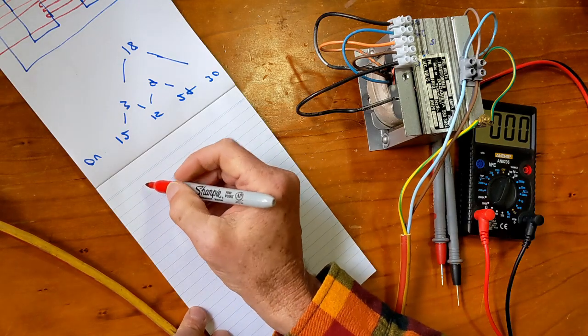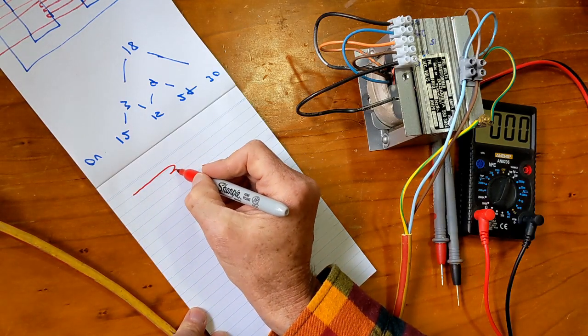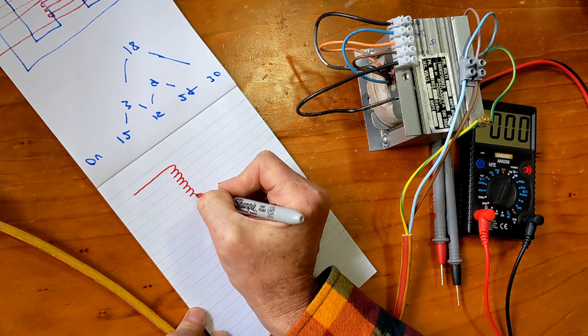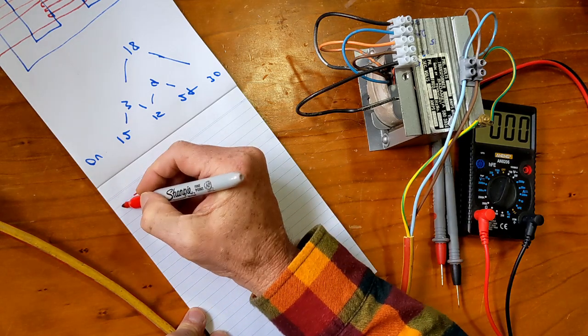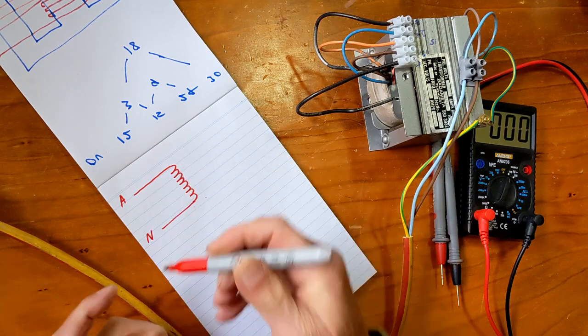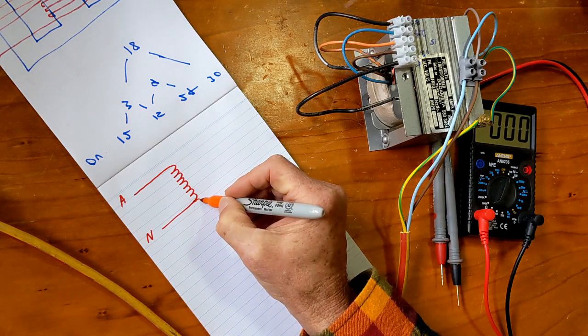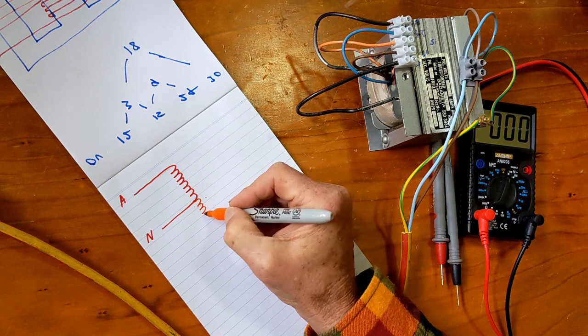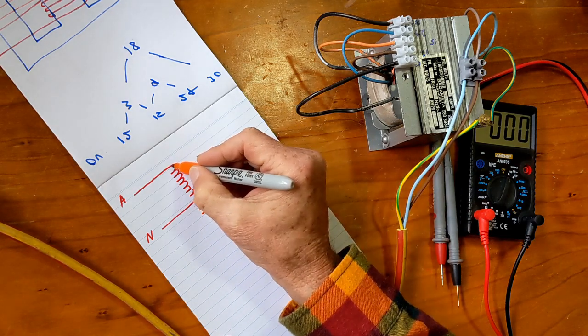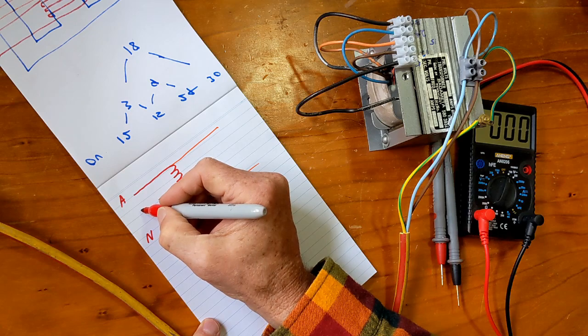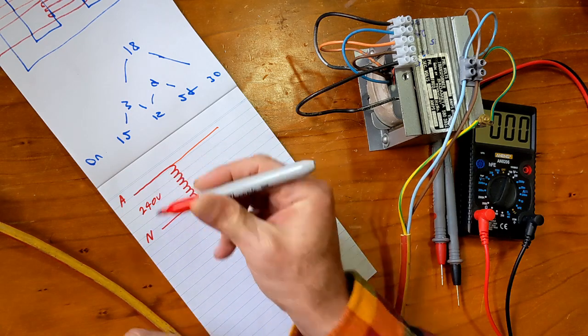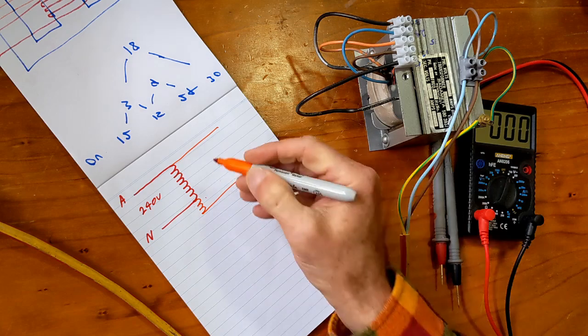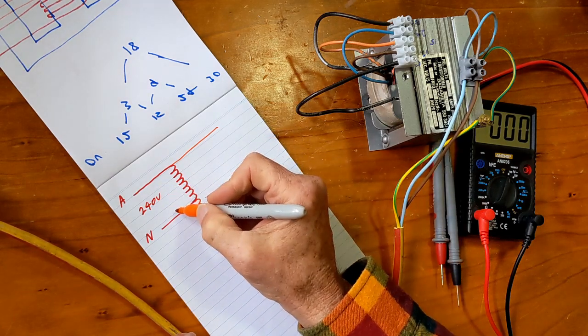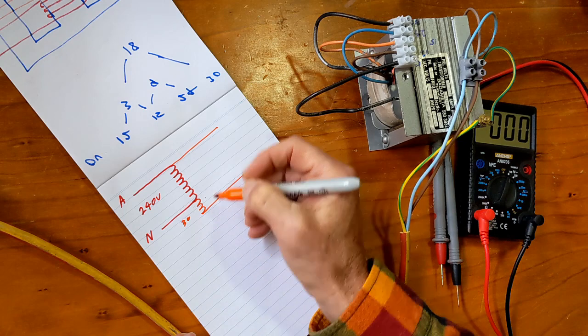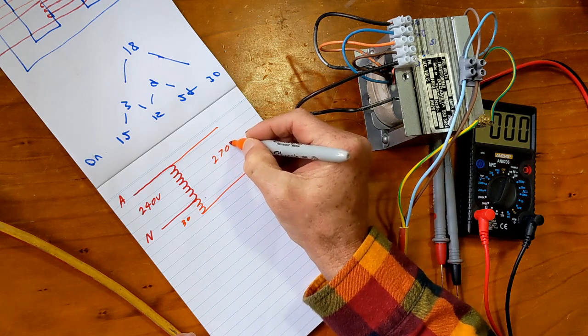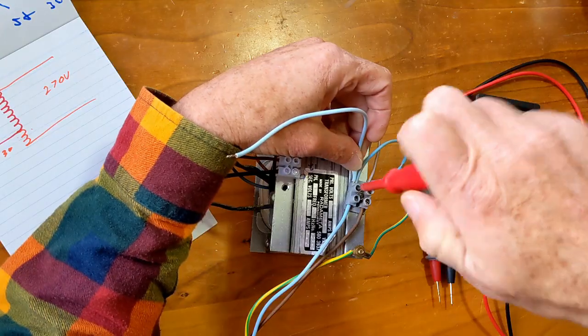So here's how it's going to work. On the primary side, I'm going to connect a lot of windings directly across the supply, active and neutral. I'm going to connect the secondary of the transformer in the same direction, and I'm going to connect the supply. So on the primary side, I will have 240 volts. On the secondary side, I'll have the 240 volts plus another 30 gives me 270 volts. So let's see what happens.